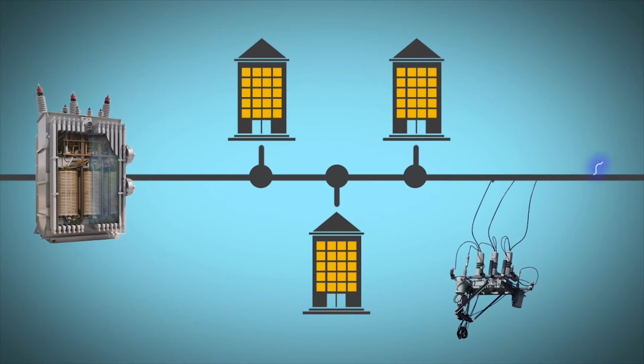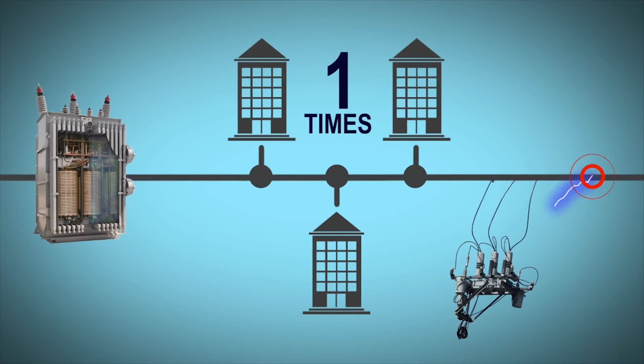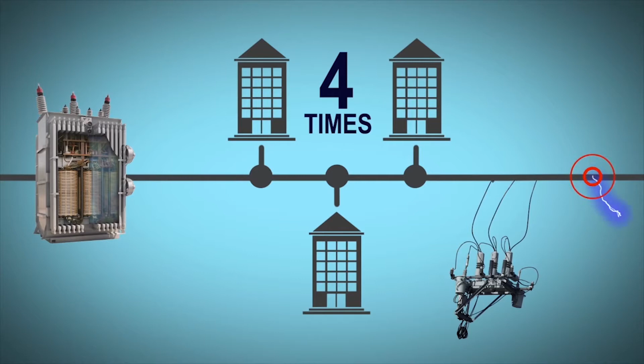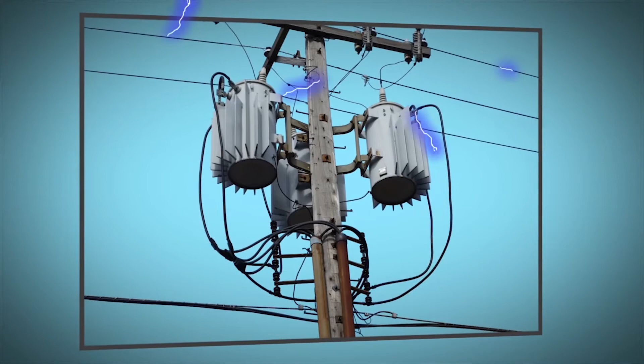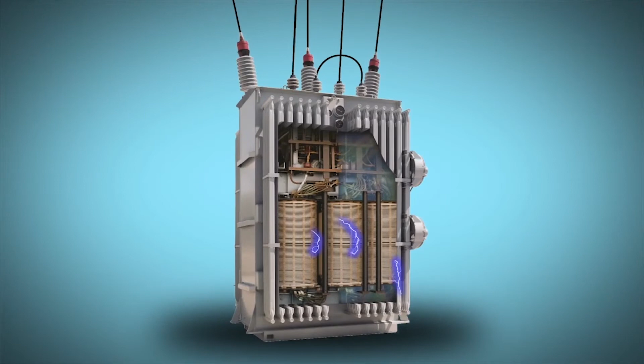The problem is, reclosing contributes to overall system reliability issues by putting the full force of the fault back on the distribution system up to 4 times. With this fault multiplier effect, reclosing takes a small problem and can turn it into an even bigger, more expensive problem. This can cause a great deal of damage to distribution equipment, such as cable joints or jumpers, and over time, it also wears down substation transformers, subjecting windings to hundreds of thousands of pounds of unnecessary mechanical forces that look like this. It's time for a better way.